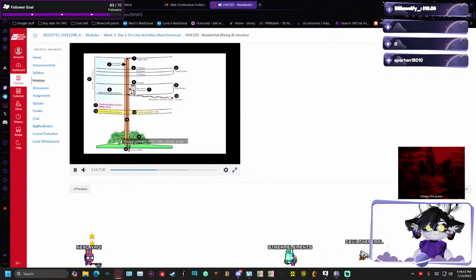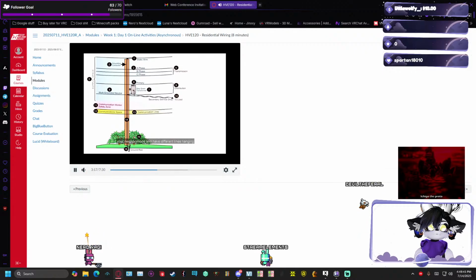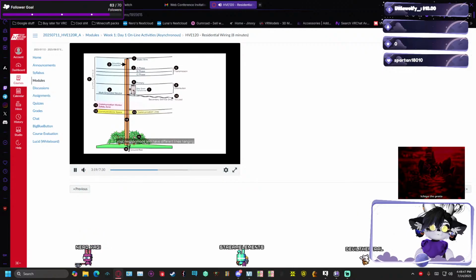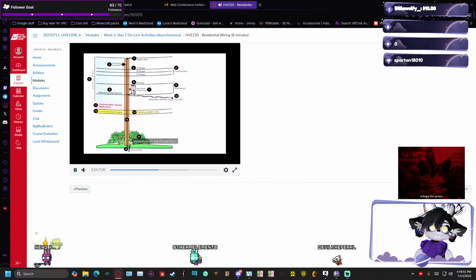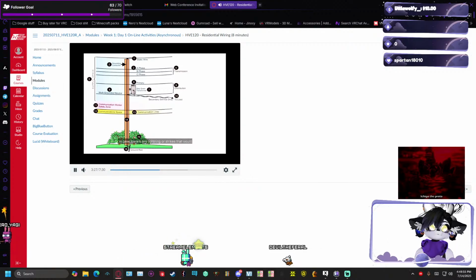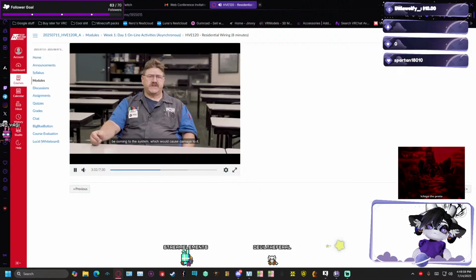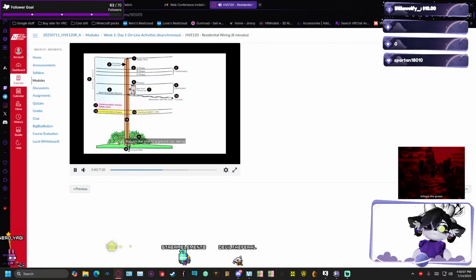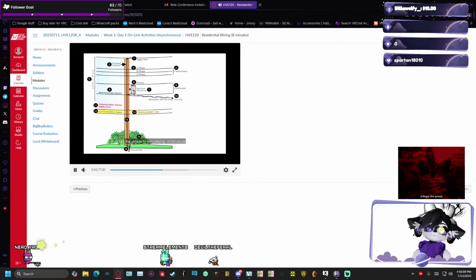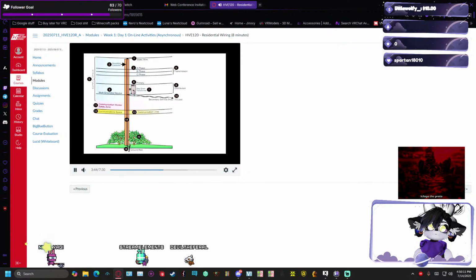You've probably seen many power poles in your neighborhood with different lines hanging on them or transformers hanging on them, as in the slide show on the PowerPoint now. The top wire is a static wire. That is designed in case there's any lightning or strikes that would be coming to the system which would cause damage to it. To subside the damage, it has a conductor going down through the pole to a ground rod, taking the voltage to zero plane, which would clear it.